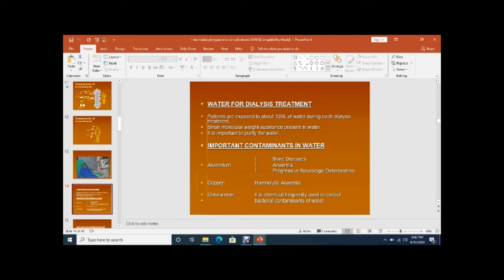Purified water is essential for dialysis treatment because each patient is exposed to about 120 liters of water during each dialysis treatment. Small molecular weight substances present in water make purification important. Contaminants in water include aluminum, copper, and chloramine.